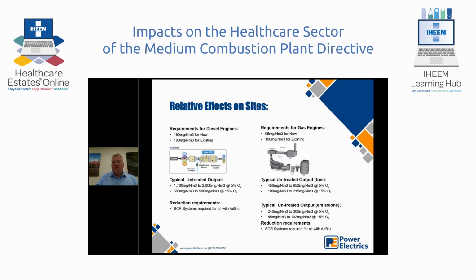The standard is derived at 15% oxygen, but most OEMs will go between 5 to 7% when they give you the NOx levels of their engines. So you need to extrapolate that to 15%. A diesel engine at 15%, a fairly modern one, will be running between 600 and 900 milligrams. Now to get down to a level of 190, you can see there's a fair level of abatement involved, so really you're going to have no other option than to use an SCR device with an AdBlue dosing system, which I'll discuss later on as well.